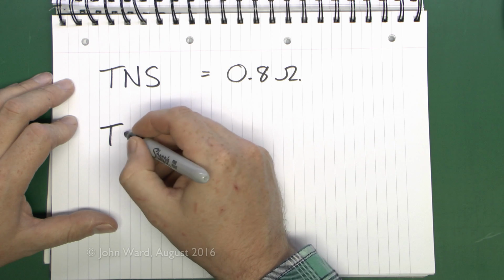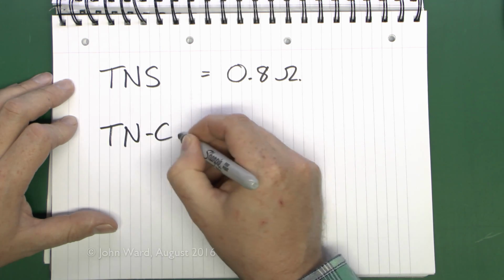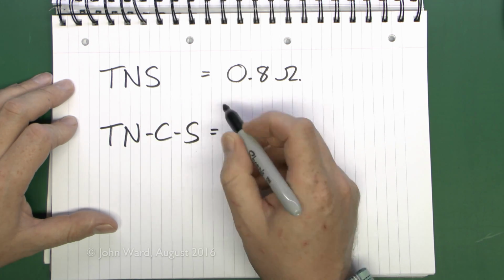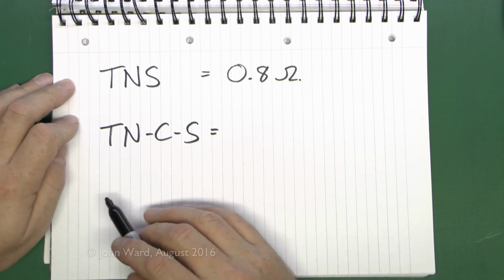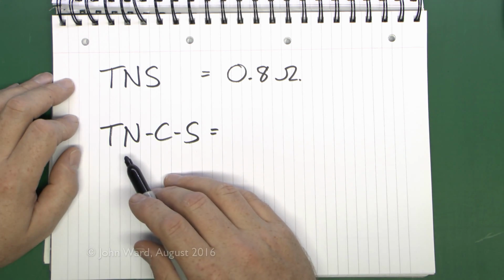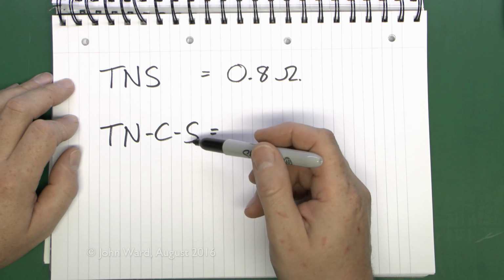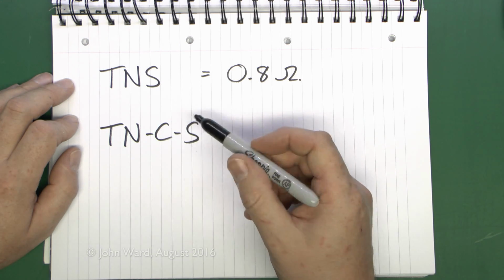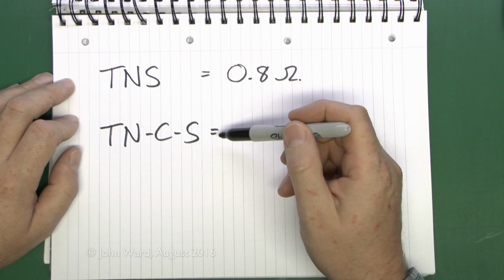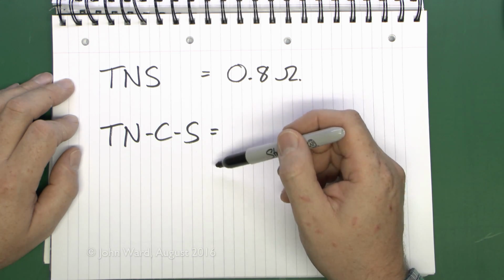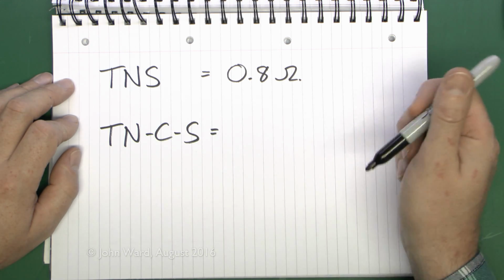And the other most common type is the TNCS system, and this is usually where you have a two-core cable from the supply, so just the line and neutral, and then the earth is actually combined with the neutral in that, so when it enters the building, your earth and neutral terminals are effectively connected to the same conductor within the cable.